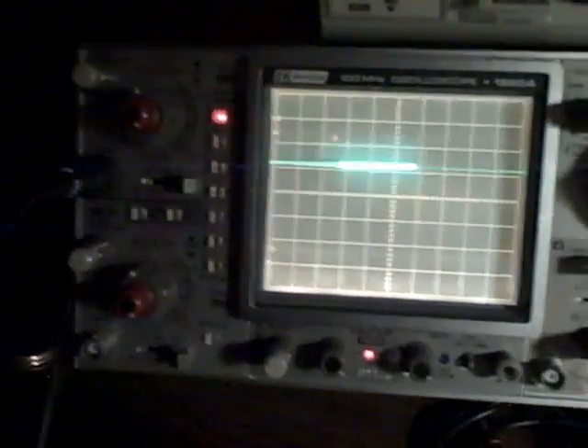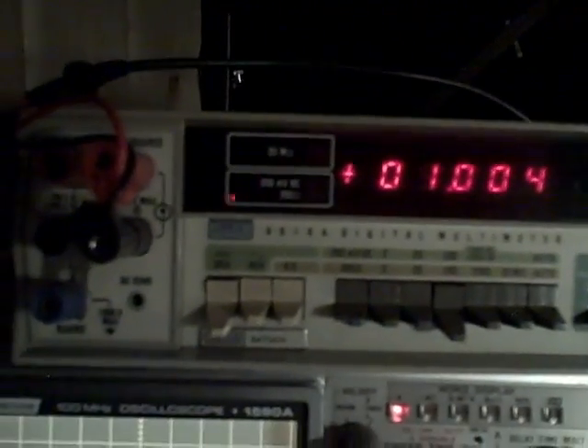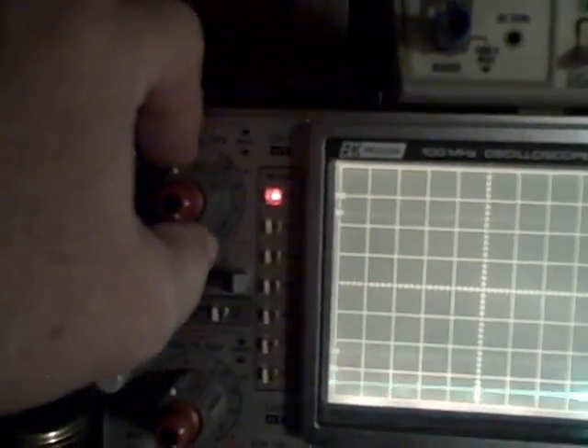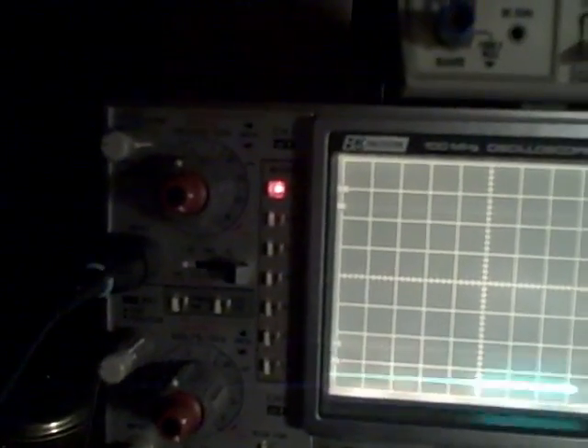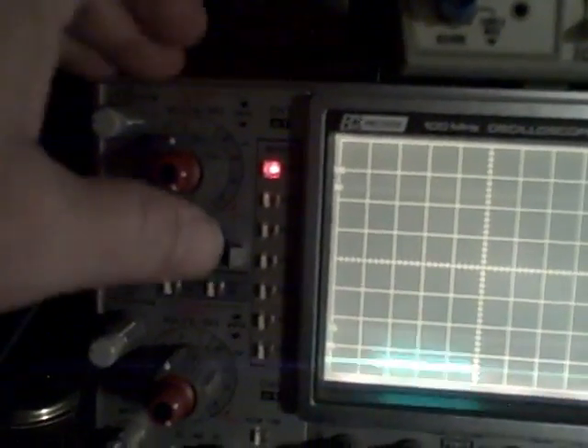Let's go ahead and cut our range down now to 1 volt. And I see that my DVM is displaying 1.004, so we're 1 volt down in the millivolt range. And there we're off by 4 millivolts. But right now I have 1 volt coming through a divider, and so I'm getting a tenth of a volt on the screen. I'm at 0.2 volts per division, and I'm displaying half a division. If I go to 0.1, I go up to a full division. I could go to 50 millivolts and jump up 2 divisions.